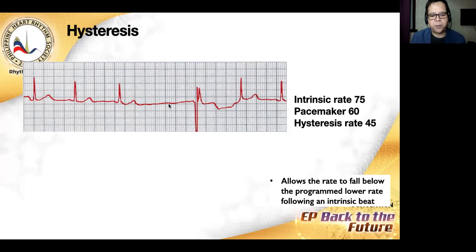But although the pacemaker is programmed to pace at the rate of 60, it allows a longer interval set as the hysteresis rate to allow the patient's own intrinsic beat to come in before it finally paces at the rate of 60. So this sort of allows the patient's intrinsic beat to come in before it paces. Right? So that's your hysteresis. So it's one way of also allowing the patient's own intrinsic rhythm to come in before you fully pace the patient.